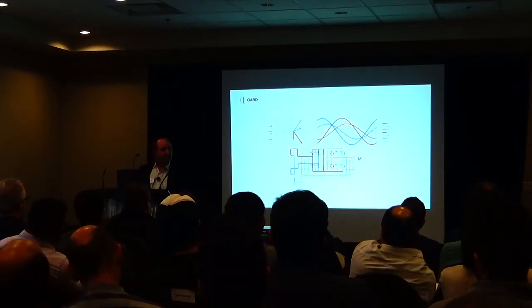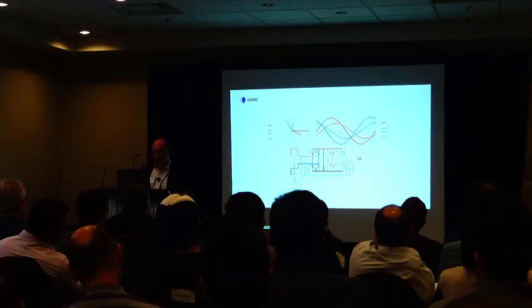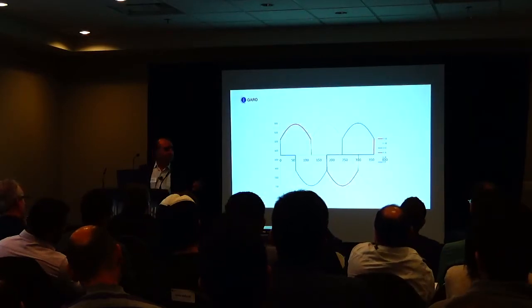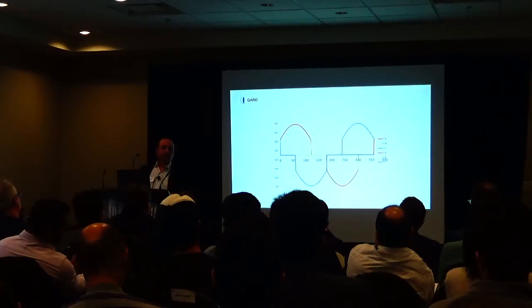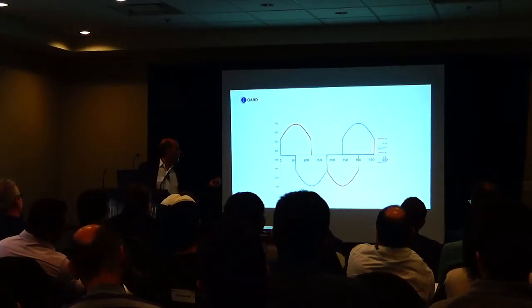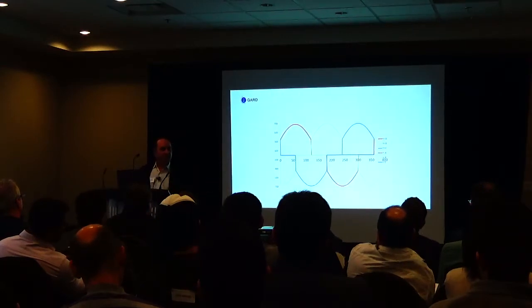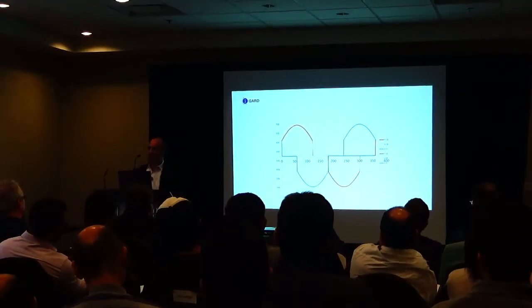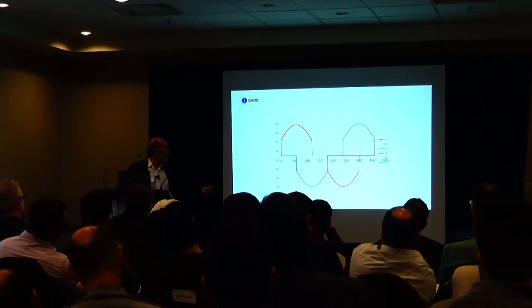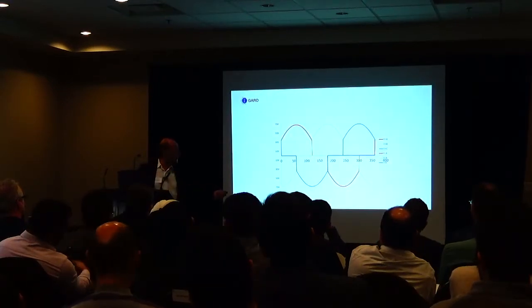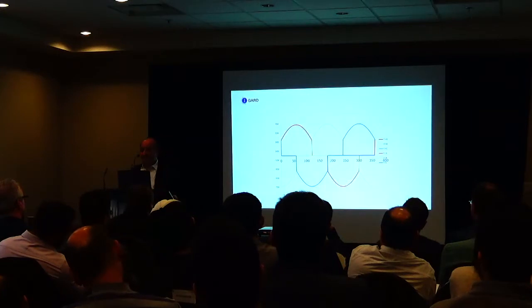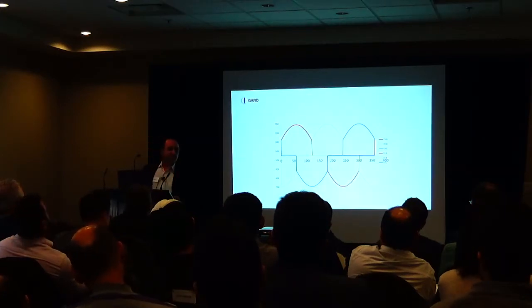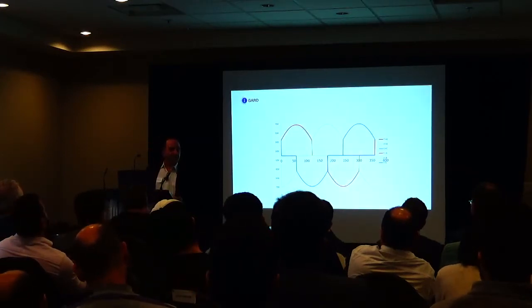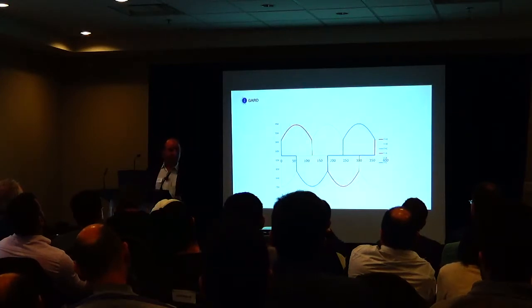2, 3. We're always forward biasing those diodes in such a manner that the DC bus, 1/3 of the time is energized by A phase, 1/3 of the time it's energized by B phase, and 1/3 of the time it's energized by C phase. And that's one cycle from here to here. These are degrees. So it's not really a separately derived source. What we're doing is time sharing the DC bus, although they're not paying the same rates you would pay in Miami.